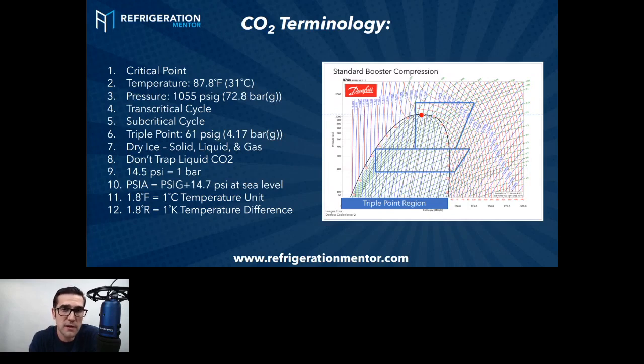I looked at tons of numbers from different manufacturers and tons of refrigerants, and CO2 can get some of the hottest water from a system. It's amazing how hot it can go, but there are design conditions which we're going to talk about. So as you can see there, when the ambient temperature is above 87.8°F or 31 degrees Celsius and the pressure is above 1,055 psi or 72.8 bar gauge, that means you're above the critical point.